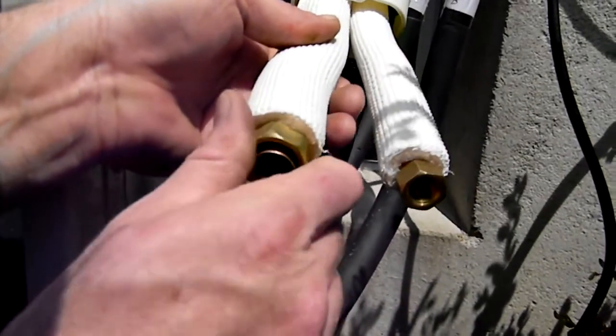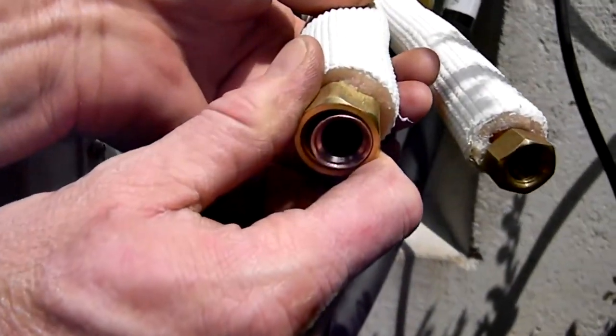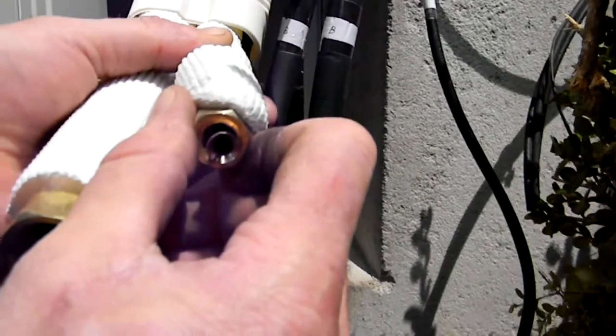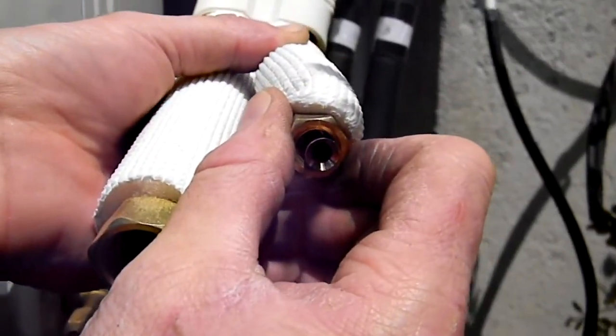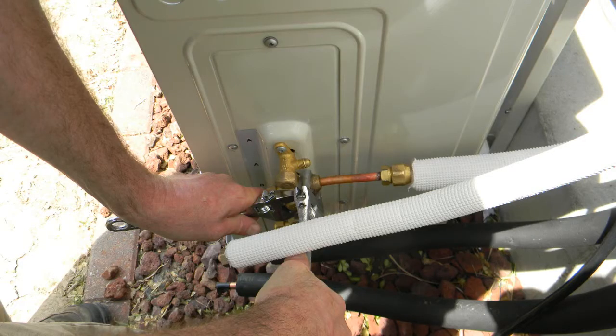If new flares need to be made, be sure female and male flare nut surfaces are clean and centered before tightening with 2 wrenches for a tight seal. Tighten all connections at the condensing unit. Make sure to connect the corresponding valves to the lines A to A, B to B, and C to C. Be careful to avoid cross piping.